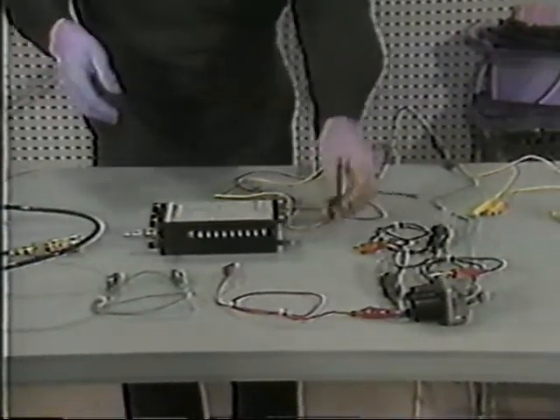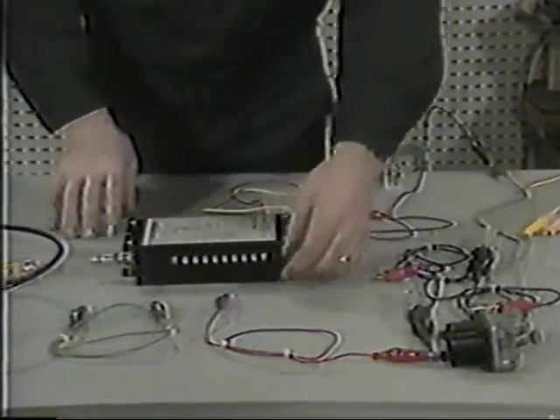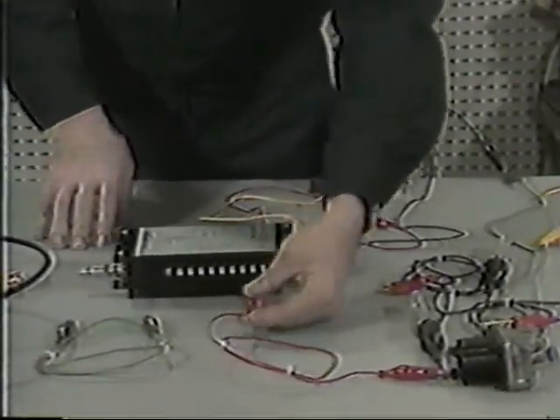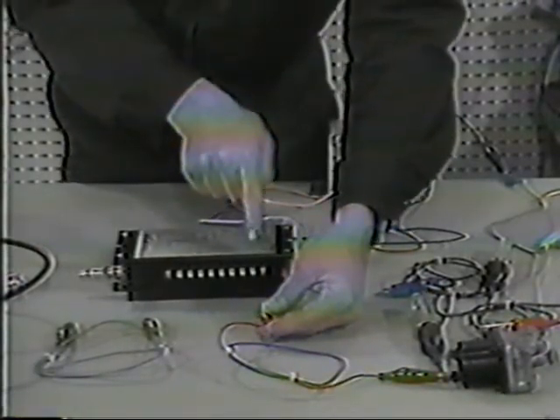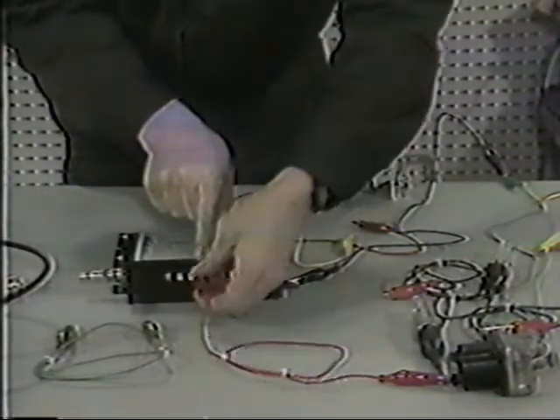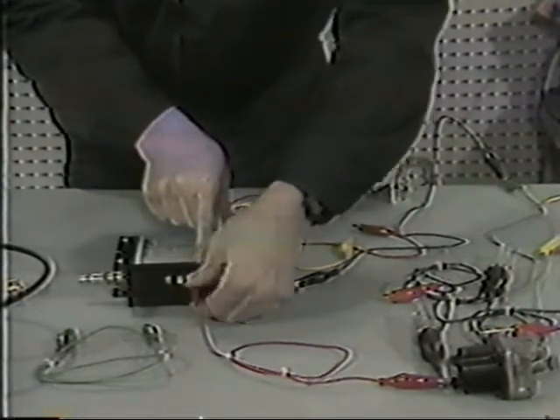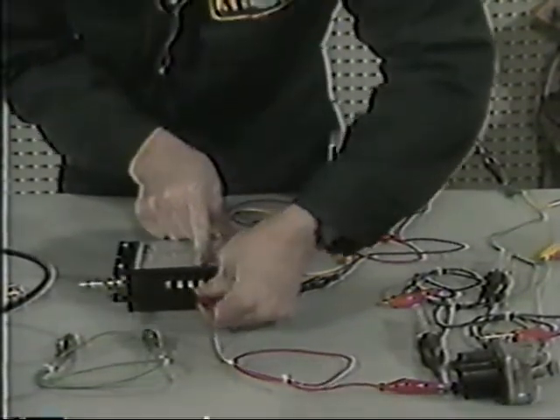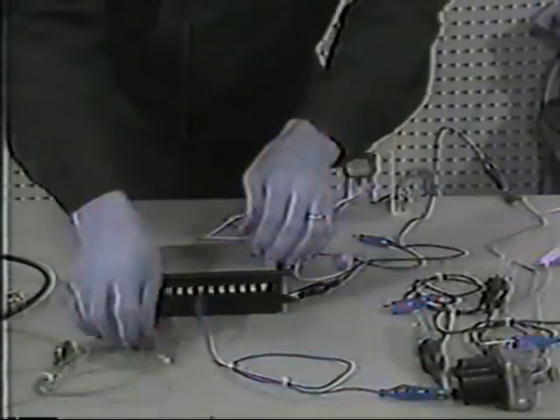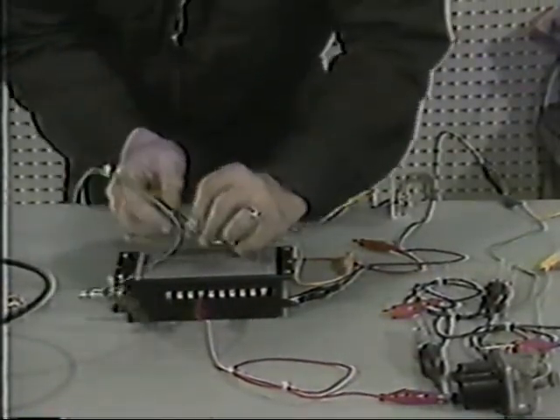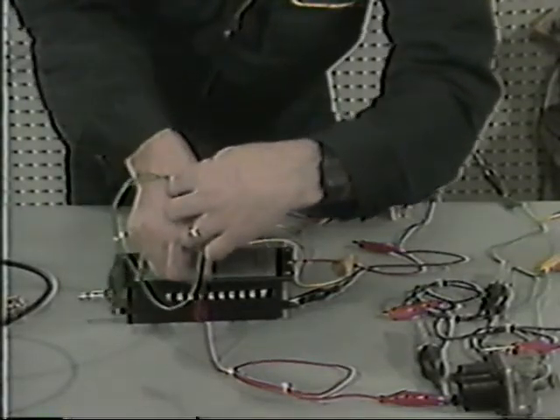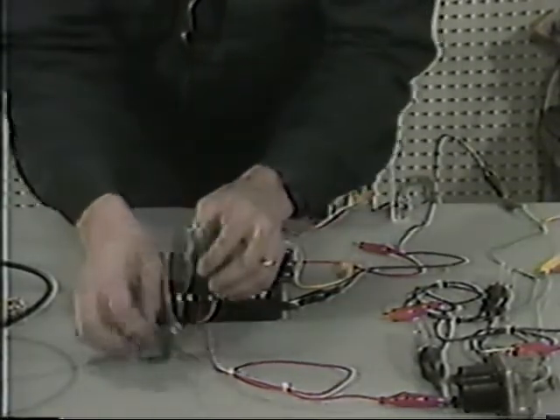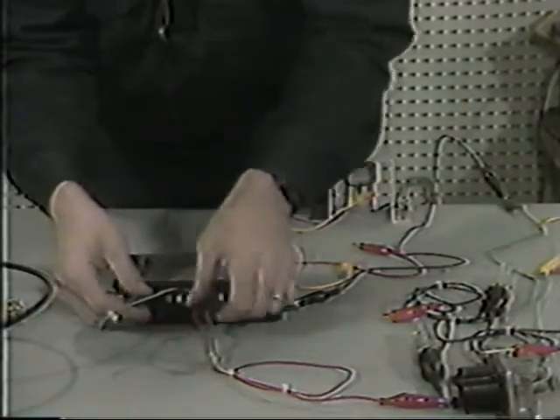Begin the test procedure by grounding the mounting tab on one end of the module. If there's any paint on there, make sure it's been scraped off. Then connect the fuel solenoid load wire to the override terminal, which is the 6th one down on the module. Take another jumper wire and connect that same override terminal to the common terminal, which is the 8th one down on the module, or the one at the very end.